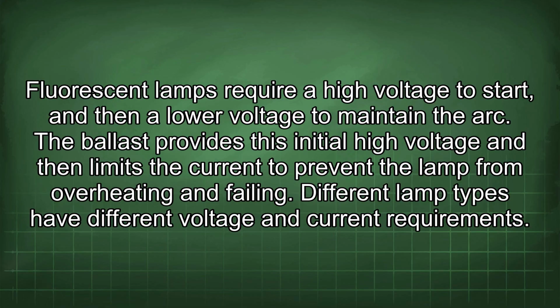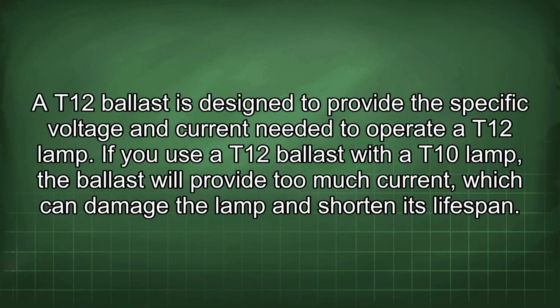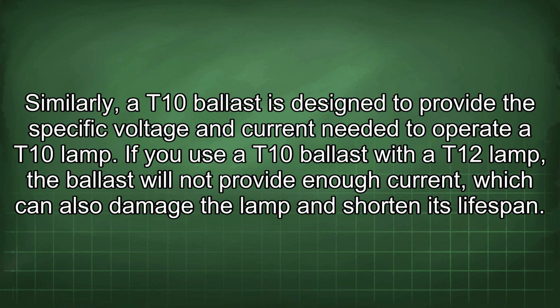Different lamp types have different voltage and current requirements. A T12 ballast is designed to provide the specific voltage and current needed to operate a T12 lamp. If you use a T12 ballast with a T10 lamp, the ballast will provide too much current, which can damage the lamp and shorten its lifespan. Similarly, a T10 ballast is designed to provide the specific voltage and current needed to operate a T10 lamp. If you use a T10 ballast with a T12 lamp, the ballast will not provide enough current, which can also damage the lamp and shorten its lifespan.